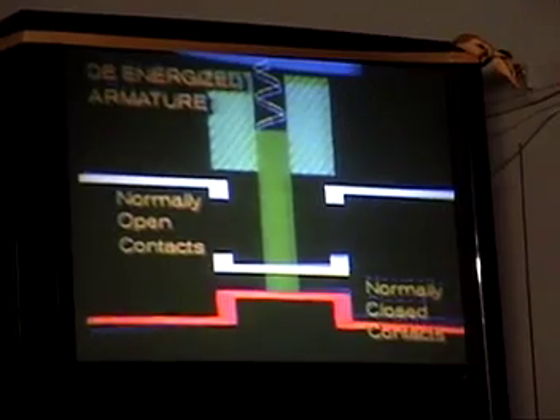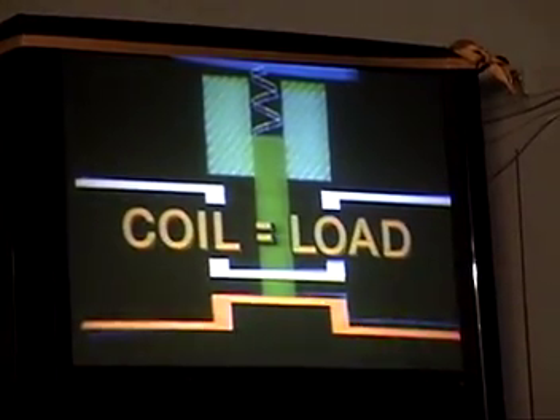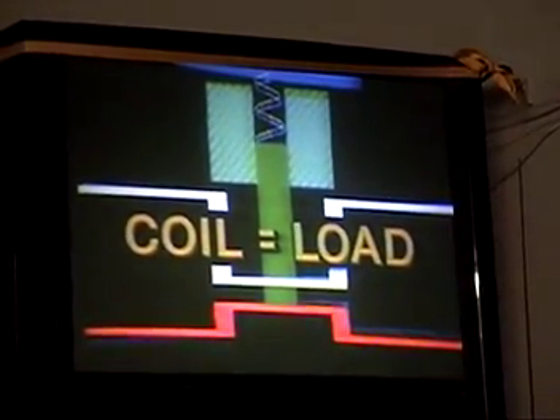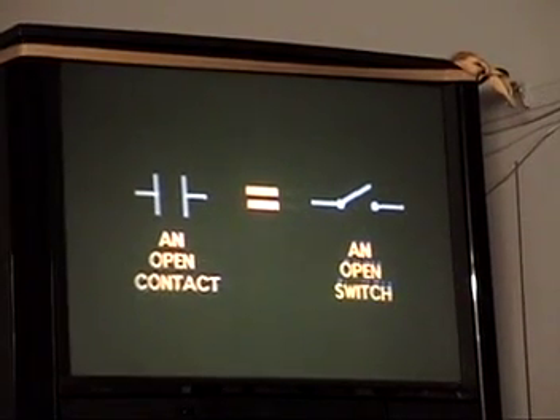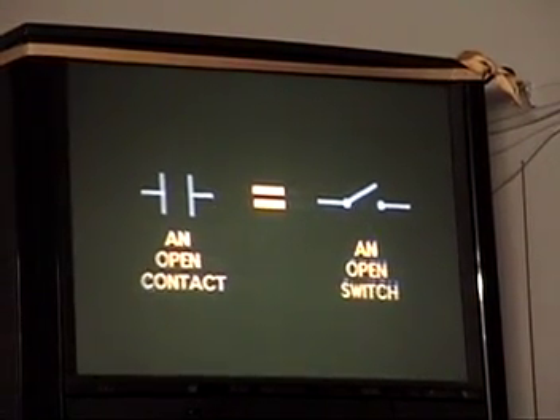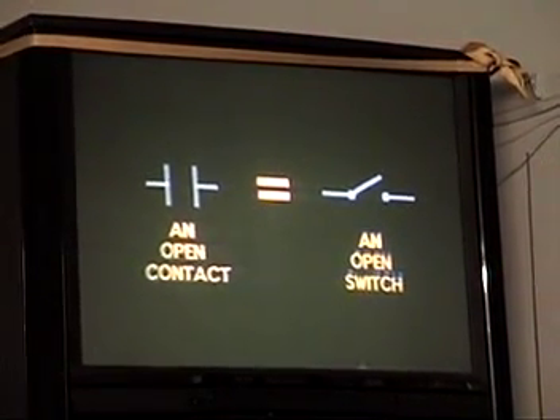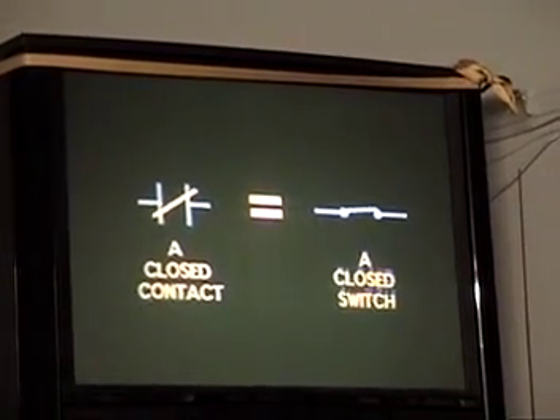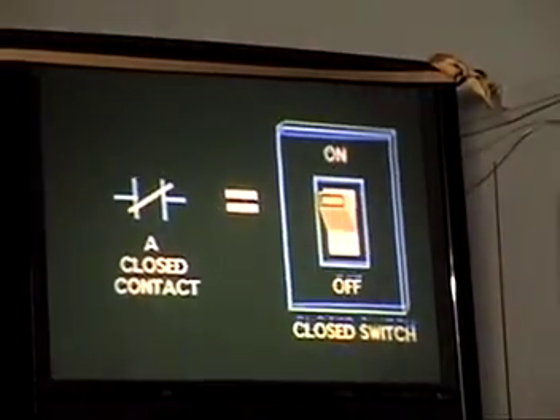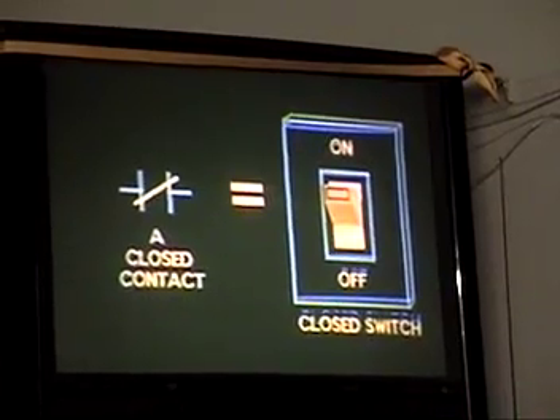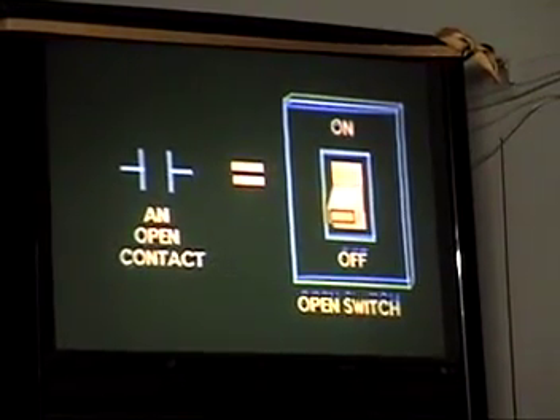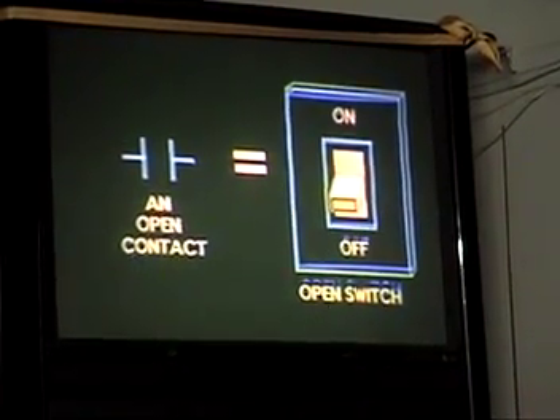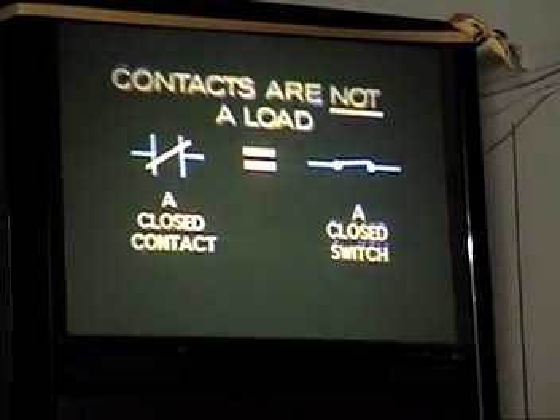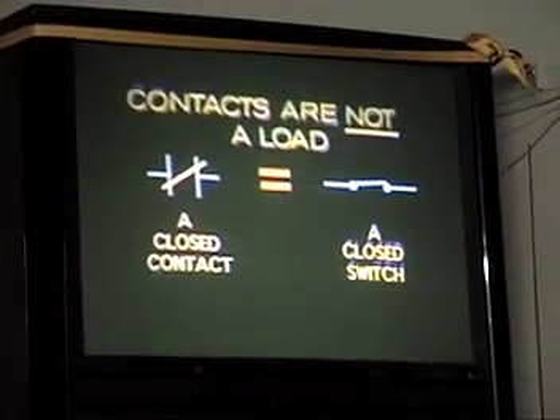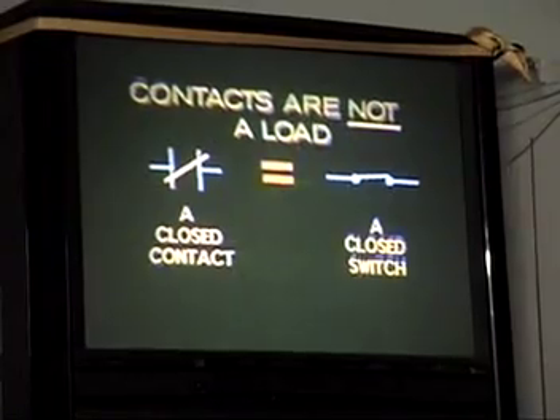In many electrical circuits, a coil like this one is the load in the circuit. The symbol for contacts will usually be shown in the position they are in when they have no power on the coil. The closed contact has a diagonal bar indicating a closed circuit. The open contact is shown without a bar. Contacts are a form of switch and only conduct electrical flow. They're not a load, but they can carry voltage to a load when closed.